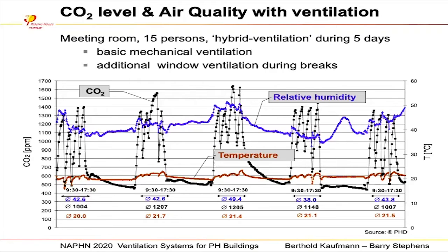And here we showed just this is out of a meeting room in Darmstadt, and it shows a so-called hybrid ventilation during 5 days. As the ventilation system is a little bit too small, it will only be able to keep the air good for about 2 hours with its 15 people. And in breaks, you may open windows if people stand up and so on. So it's no problem. Well, but in meantime, the CO2 level with the ventilation system can be kept quite below this 1,500. So about 1,200 or something, it's quite good.